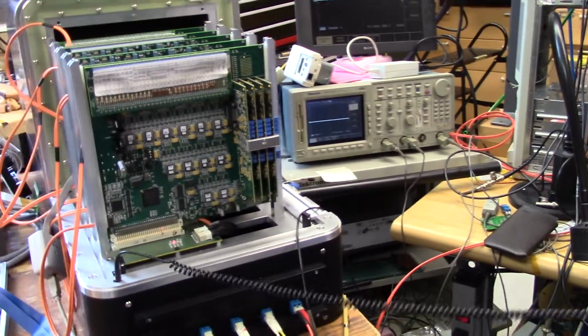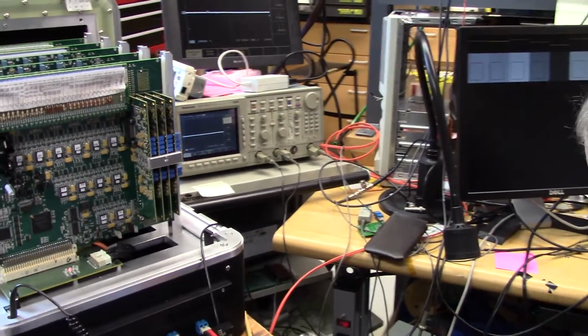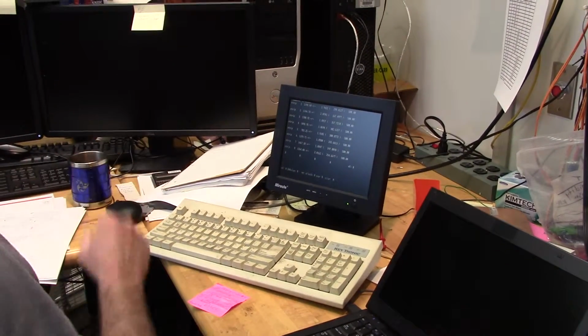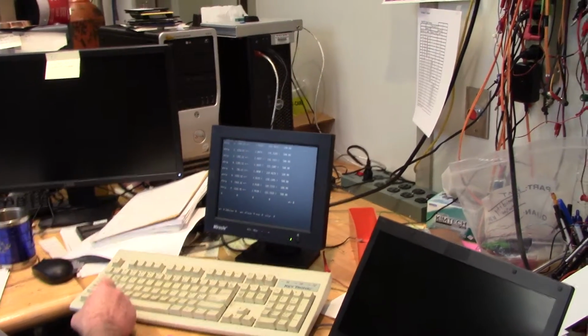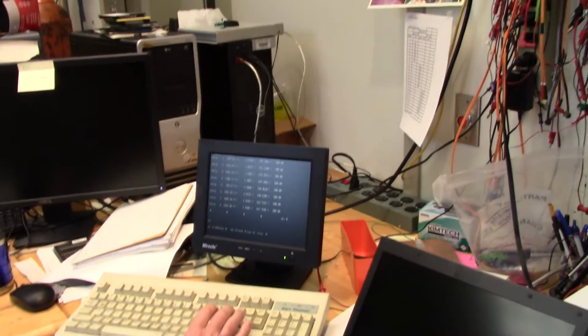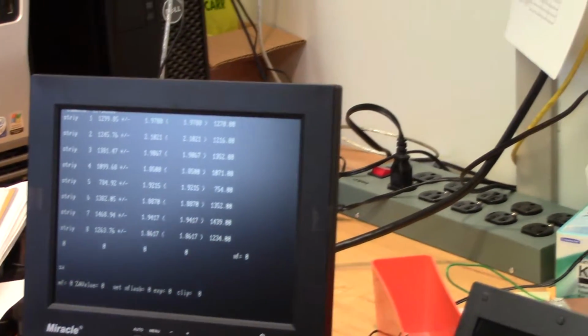Okay, so let's turn the noise maker back on. And we've got to get the program doing what we want it to do. I'm still tied to the box here with my strap. There is just a huge number of commands in the program, but I think if you just bring it up and do a ZA, which will automatically zero the signal on the display, you see now the signal is near 0, believe it or not.